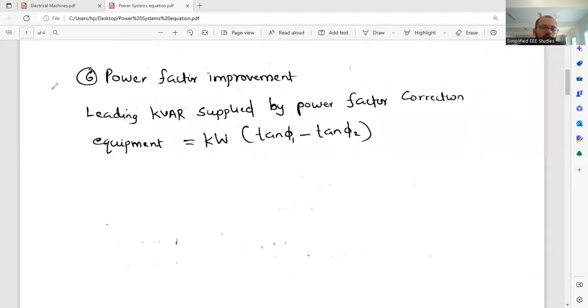Now, there is another important equation, power factor improvement. Leading kVAR supplied by the power factor correction equipment. There is a derivation. The result will be kilowatts into (tan phi 1 minus tan phi 2). This important equation you also have to remember.